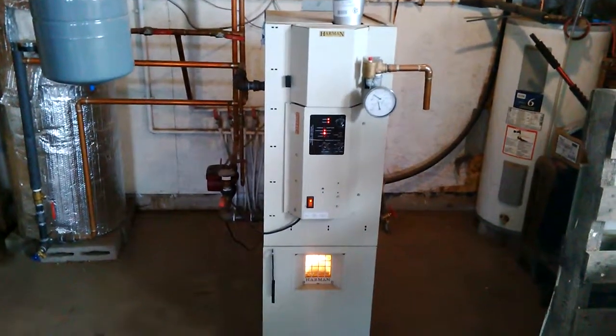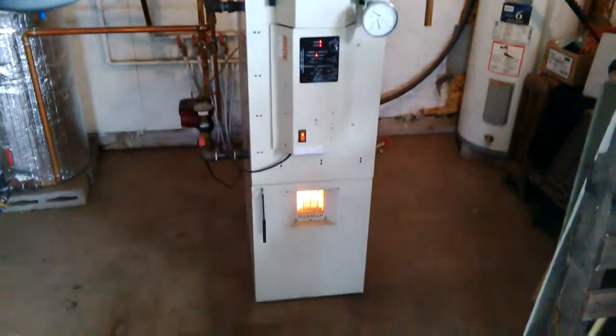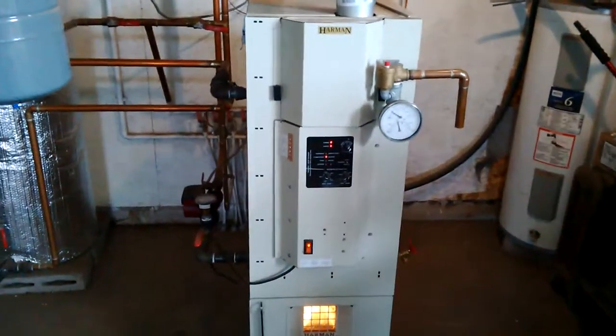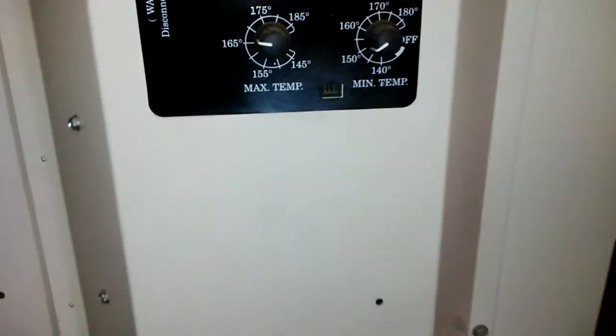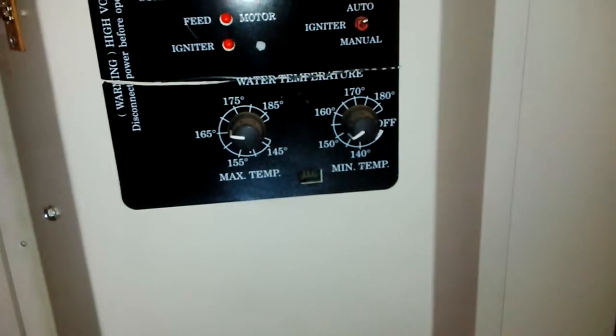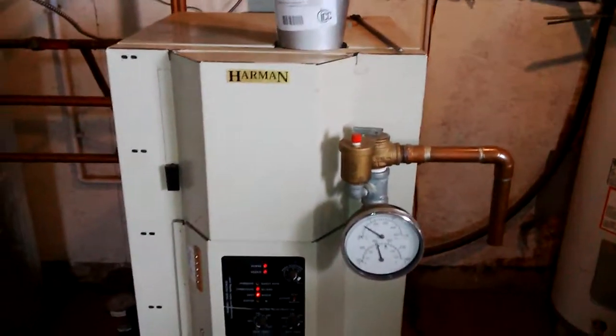Hydroflex 60 installed in my house, burning fine. I just want to show how we plumbed it up to a buffer tank and basic controls. I have my feed adjustment turned all the way up to number six. I'm going for a high temp of 165 and a low temp of 150. I have a really good fire going — everything pretty much gets burnt up before it tips over the end, so I'm able to have my feed rate turned up. The unit is smart enough to actually modulate itself to allow for the demand on the house.